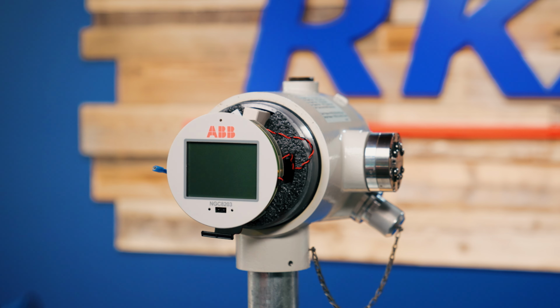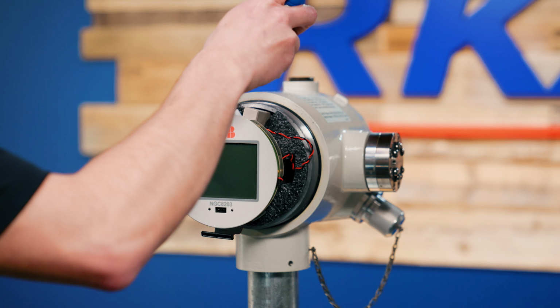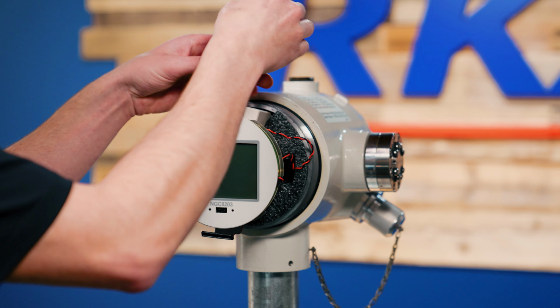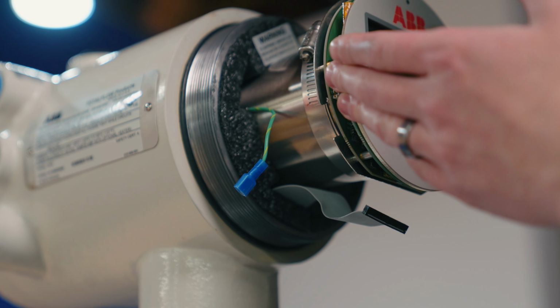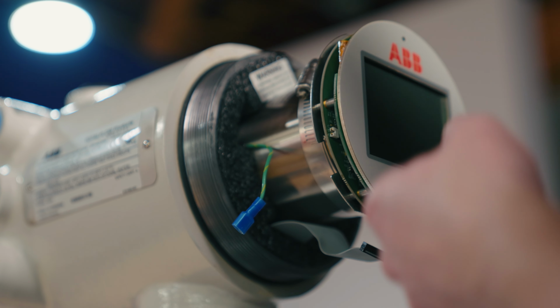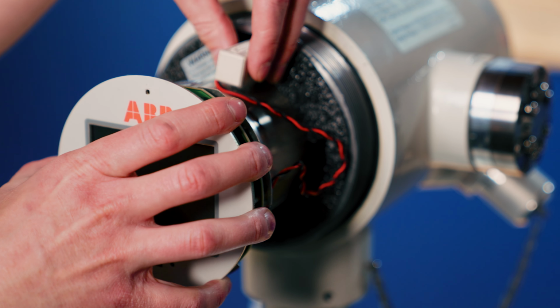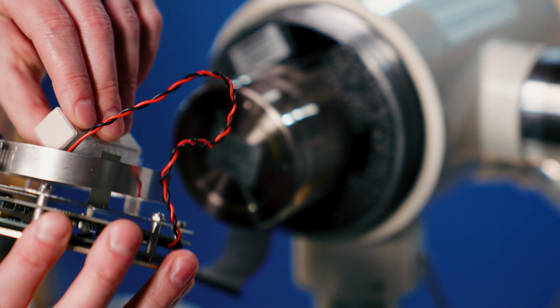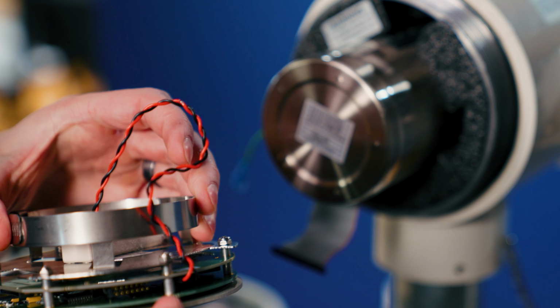Now that both cables are disconnected, we can remove the display from the module by loosening the hose clamp and sliding the display off, keeping in mind that we need to keep the backup battery connected to the display.